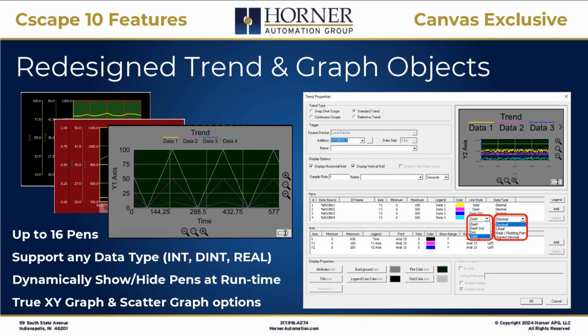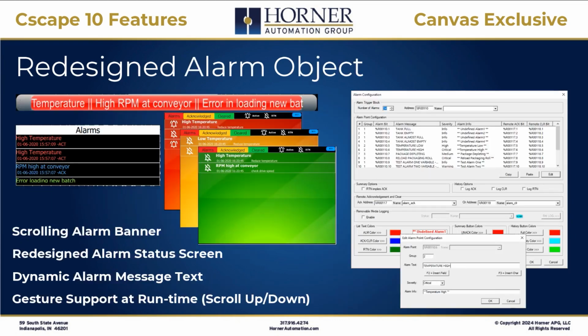And then from a graph standpoint, we've traditionally supported what's called an XY graph, but it really wasn't an XY graph with a true X and Y variable. It was more of an XY graph where X was always time. Well, we have a true XY graph with Cscape 10, which also includes the ability to do scatter graphs as well, where you don't necessarily want to connect lines between the data points. So those are also available in Cscape 10 with completely redesigned trends and graphs.